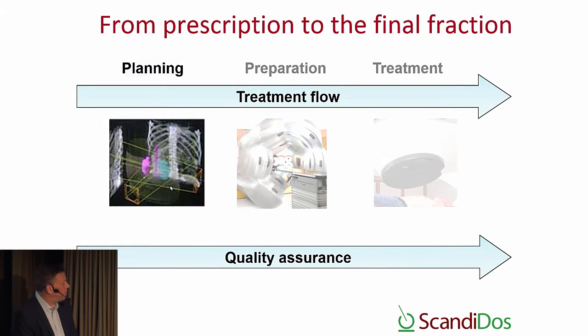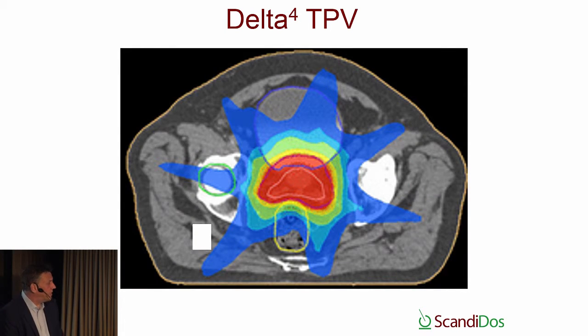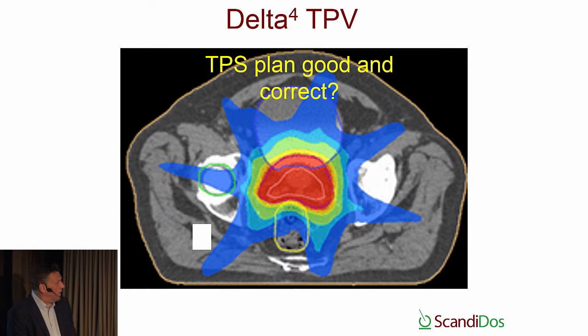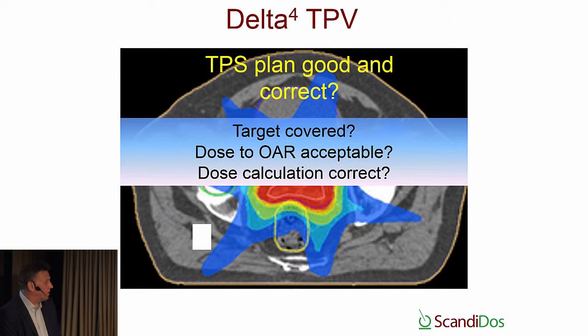Finally, I'm going to mention some about the first step in the QA process. That's the planning. So later this year, 2016, we will release the Delta4 TPV, treatment planning verification. The idea with this software, which is plan software, is to verify the treatment planning system and if the treatment planning system has correctly calculated the dose distribution. So the questions it will answer are: is the target covered? Is the dose to the organs at risk acceptable? And is the dose calculation correct?